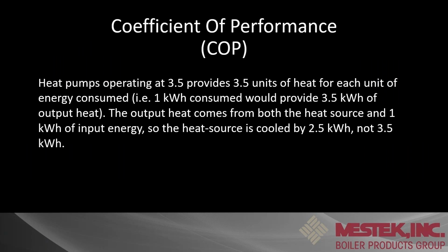Again, to touch on that COP, coefficient of performance, to keep this simple, I'm going to explain it like this. If I spent $1 for electricity and I had resistance baseboard, let's say, I'm going to get $1 of heat out of it. Now if I use an air to water heat pump, or any air source heat pump, if I spend $1, I could get up to $3 worth of heat out of it. That's how we're doing that. We're taking that energy out of the air and putting it into the refrigerant. We are using electricity to deliver this, but we're getting more bang for our buck by using a product like this.